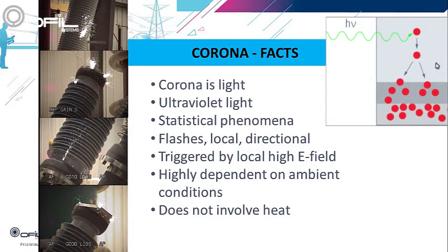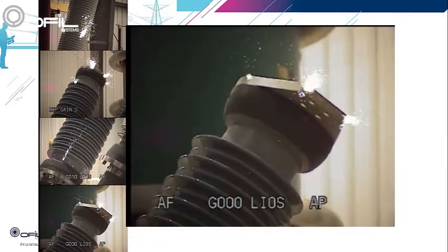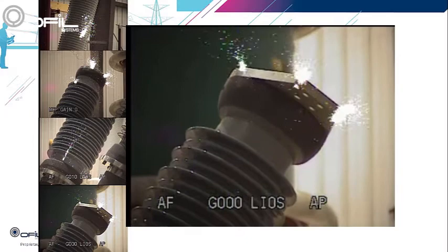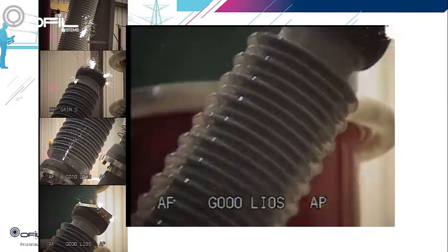Corona is a statistical phenomenon. It involves quantum chemistry, ionization, and recombination processes. The discharge must get started by either cosmic radiation or by an electron that has detached from negative ions during previous discharges that are still present. Corona flashes — it is local and directional, triggered by a locally sufficiently high electrical field of at least 3 kV per millimeter.